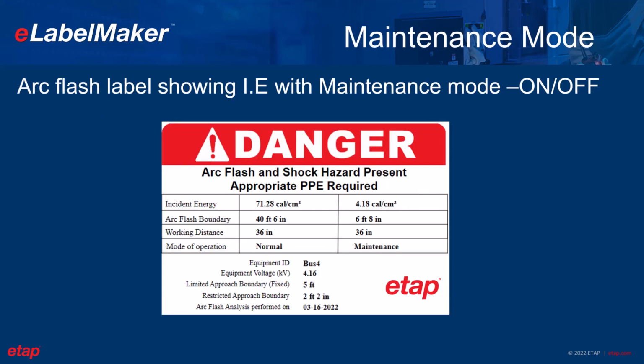The next main important feature that we included in this tool is the maintenance mode. An arc flash label showing an incident energy with maintenance mode on, maintenance mode off. So this particular feature in the ELabelMaker would be of great use on locations where the incident energy could be used to show two different sets of values in one label.